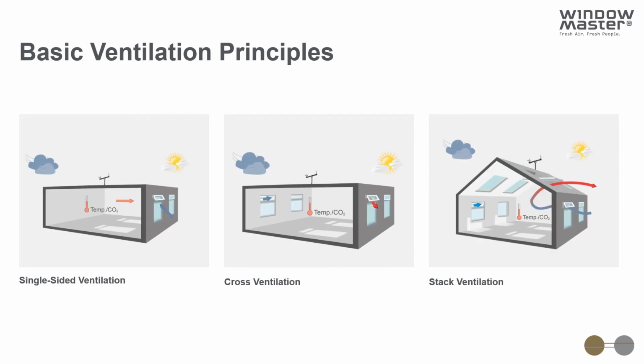Typical guidance is that single-sided ventilation should be used in rooms of no more than 2.5 times the maximum ceiling height for the room depth. For cross ventilation, it's typically 5 times ceiling height as a maximum room depth. We would always recommend cross ventilation wherever possible. Single-sided ventilation is suitable for low occupancy cellular offices around the perimeter of a building, but we would always recommend cross ventilation wherever possible. And of course, if there's large open spaces such as open plan offices with atria, then we have the opportunity to use the atrium for stack ventilation as well.